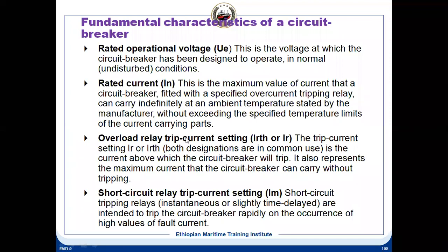Fundamental characteristics of a circuit breaker. You must have seen MCCBs. There are some basic parameters which are always important while selecting any breaker. What is the rated operating voltage? You may not find it written as V. It will be written Ue. Ue stands for rated operating voltage. This is the voltage at which the circuit breaker has been designed to operate in normal conditions.